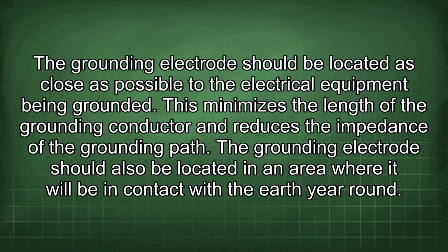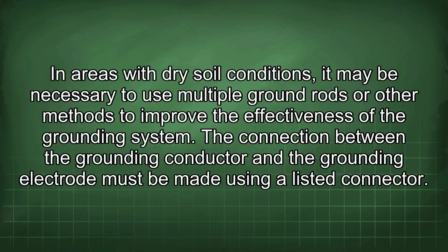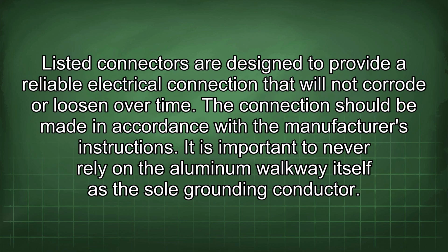The grounding electrode should also be located in an area where it will be in contact with the earth year-round. In areas with dry soil conditions, it may be necessary to use multiple ground rods or other methods to improve the effectiveness of the grounding system. The connection between the grounding conductor and the grounding electrode must be made using a listed connector. Listed connectors are designed to provide a reliable electrical connection that will not corrode or loosen over time. The connection should be made in accordance with the manufacturer's instructions.